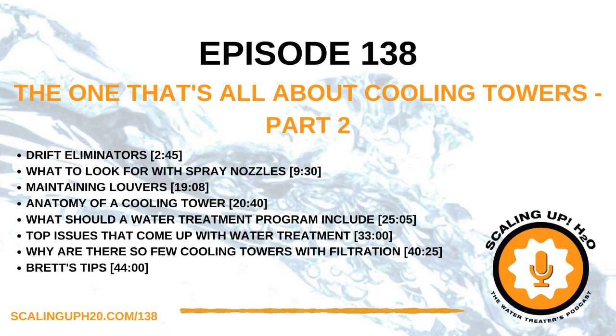Something that we like to do on a regular basis is go up and take off the easiest piece of drift eliminator that we can access, making sure that we've either turned off the fan or whatever we needed to do to keep ourselves safe. And then we look down below that to inspect the spray nozzles. So I thought we would bring this up since we were talking about the drift eliminators, but what should we be looking for with the spray nozzles?